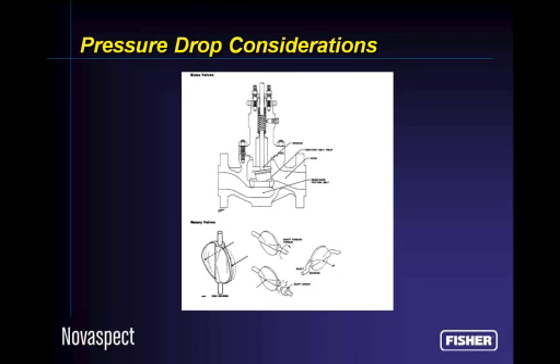As you would expect, pressure difference across a component times the area of the component is a force. Pressure times area equals force. So differential pressure across areas in the valve will produce various forces that are detrimental: bending, shearing, things of this nature. It could be a globe valve, where we want to twist the plug off the stem. In a butterfly valve, we might actually want to break the shaft and let the butterfly valve disc go downstream.